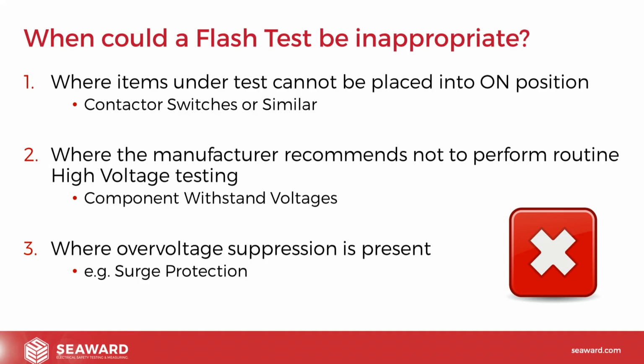Now, this may not be possible with certain products. So if they have any kind of electronic switch where we physically cannot place the switch into the on position before the test, it may not be relevant to do a flash test. Again, anything with a trigger, where the trigger can't be locked on, we may have the same kind of issues. We may find that the manufacturers recommend that we don't perform a high voltage test at all. It could be that components used inside the product are not suitable for high voltage testing. The manufacturer ultimately remains the authority on his products.